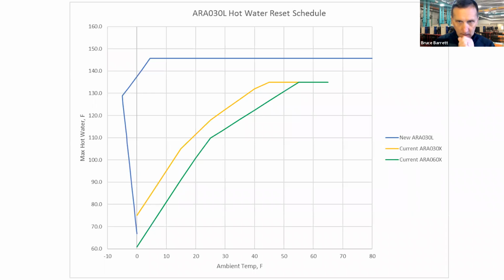Again, an eye chart, but the green line is our ARA 60X. On the bottom is ambient. On the left is the temperature of hot water. So you can see somewhat our reset schedule with the on-off technology. Once we get to about 30-degree ambient, I start losing the quality of water. The big line, the most important line, is the blue line up top, which is the refrigerant injection scroll. We call the ARA 30L. I can go all the way down to zero. It greatly expands the operating envelope.